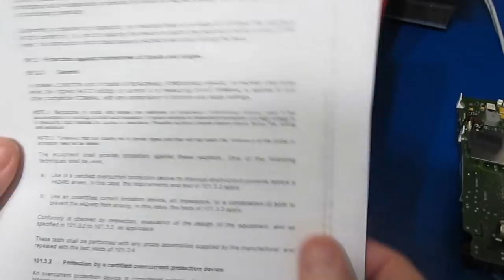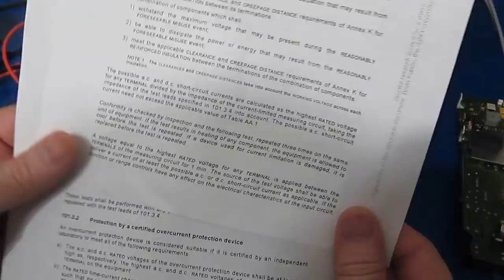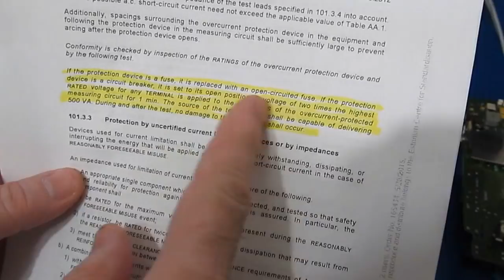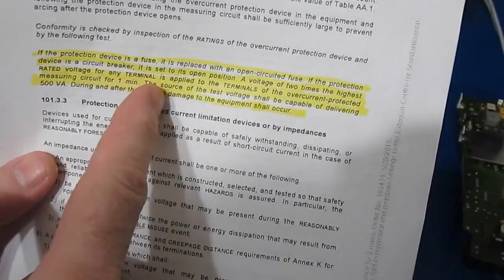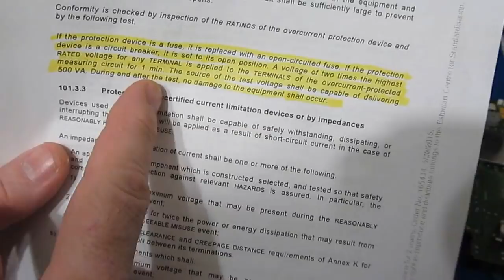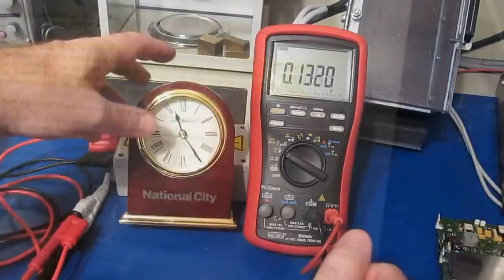If you're curious where I'm getting this from, this is out of 61010-2-033, section 101.3.2. Here we can see: if the protection device is a fuse, it's replaced with an open-circuited fuse. A voltage of 2 times the highest rated voltage for any terminal is applied to the terminals of the overcurrent protected measuring circuit for 1 minute. The source of the test voltage shall be capable of delivering 500 VA. During and after the test, no damage to the equipment shall occur.